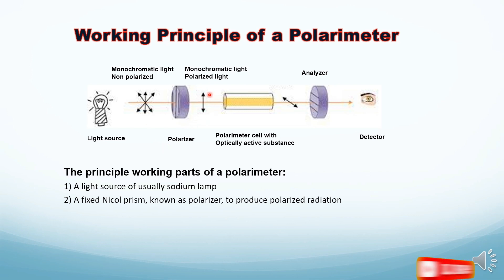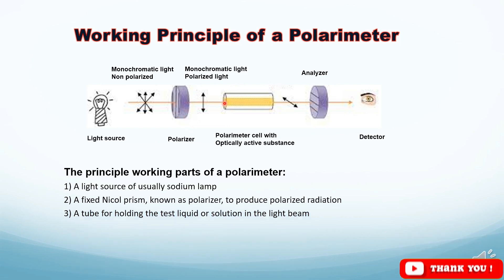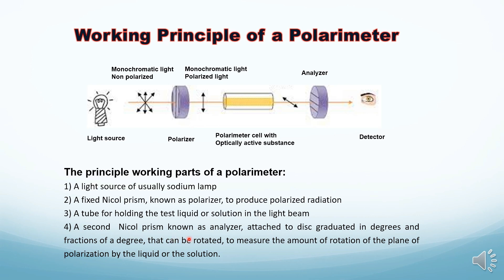This plane polarized light passes through a tube which is used for holding the test liquid or solution in the light beam. This tube may be empty or it may contain the solution of the substance to be tested. Then we have a second Nicol prism known as the analyzer, which is attached to a disk graduated in degrees and fractions of a degree.